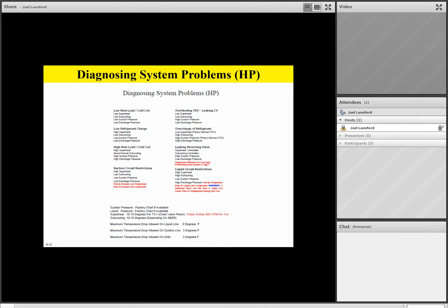Now let's take a look at diagnosing system problems a little bit closer in some of the service calls. We see, for instance, if we have a low heat load in the upper left-hand column right there, in other words, we're not getting the proper airflow across the cold coil, it's going to drive the superheat low. We'll also observe low subcooling, low suction pressure, and low discharge pressure if we have low airflow on the cold coil. Now, team, remember, the coil outside in the heating mode is the cold coil, and the coil inside in the cooling mode of operation is the cold coil.